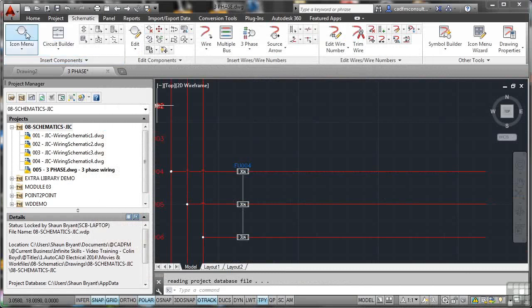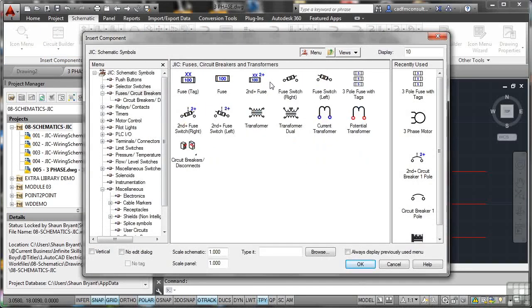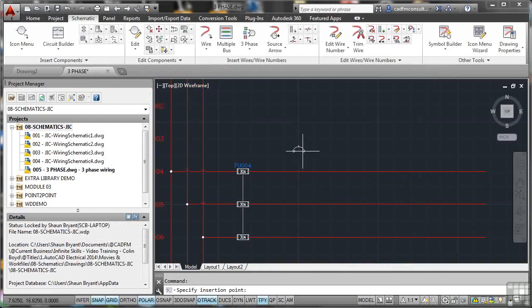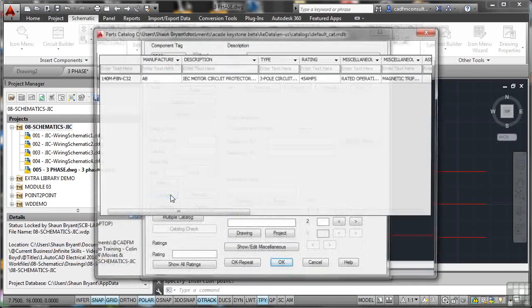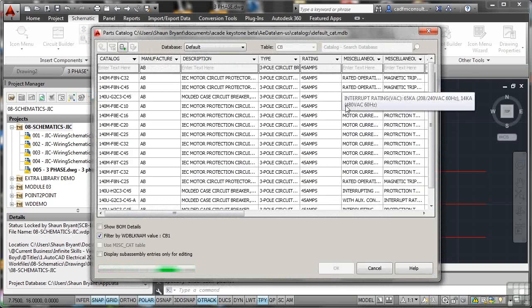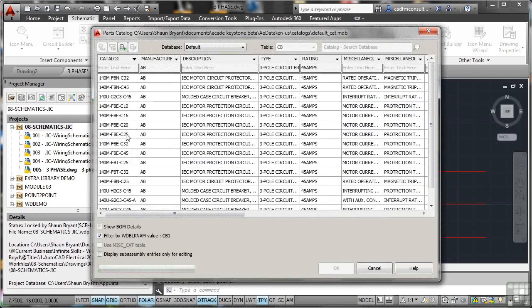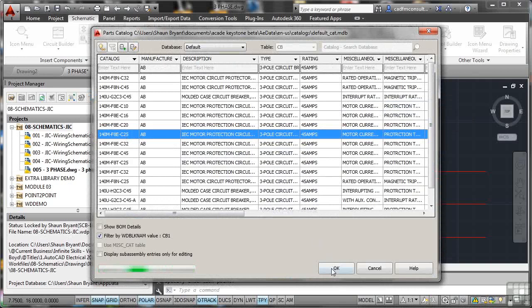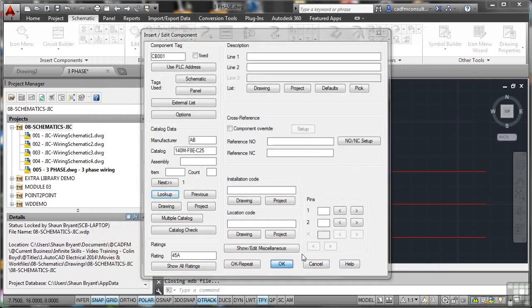I now need to add some circuit breakers before I place the motor at the end of these three wires. So I go to the icon menu again, fuses circuit breakers, and what I look at now is circuit breakers disconnects there. I'm going to go for just a one-pole circuit breaker first of all and place it just there. That's CB04. I might want to change that to CB01 just to be sequential because it's the first one there. I do a lookup again and I apply whichever one I want to use. Now, you've got lots of different ones in here, lots of different manufacturers. I'm just going to select a standard one, that one there and OK it and then OK that and that updates accordingly.